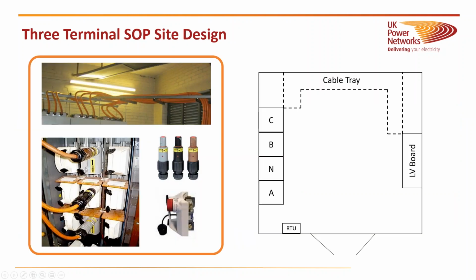So when we're designing the site, if you see here, these are some pictures which show how we're going to connect it to the LV board. It's got to connect in 3 different ways on the board. We've tried to keep it, again, as easy as possible for our operations team. So it follows a similar design to how we connect temporary generators. You have a separate cable for each phase, and then one for the neutral, and they connect onto the bus bar using these Lytton connectors and fuseways like this.